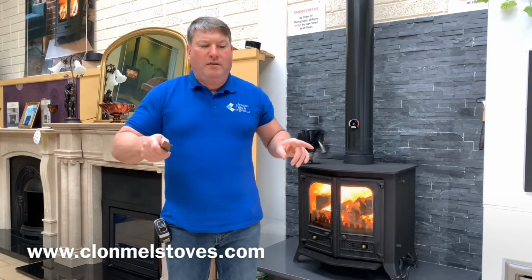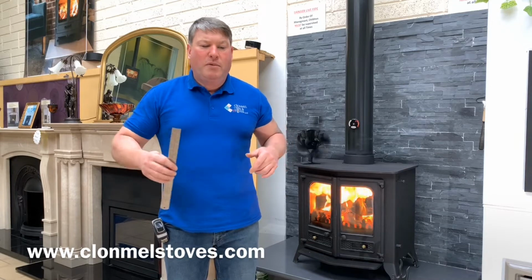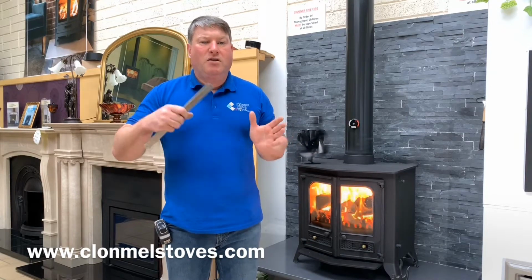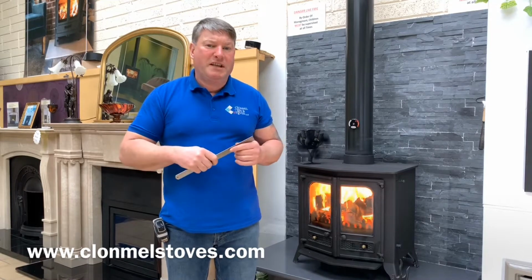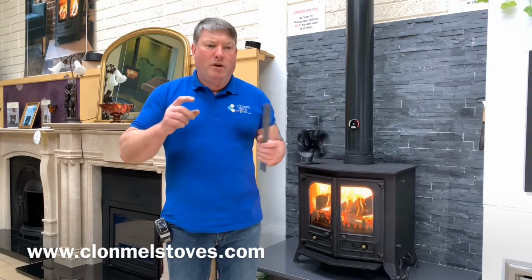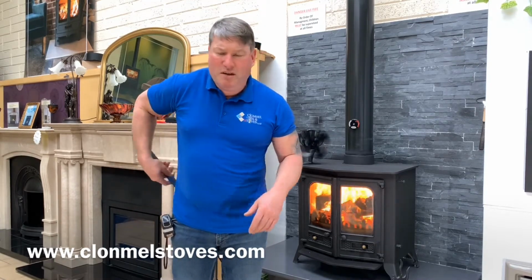You'll be doing length by breadth of the room and then the height. You'll multiply all those figures and then you'll be dividing that total by 14. You might wonder where the 14 comes into it. Well, basically 1 kilowatt will heat 14 cubic meters of air. So let's see if we can go through that with you briefly. We'll just jot it down to give you an idea of what I'm talking about.